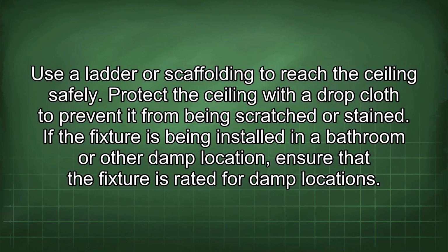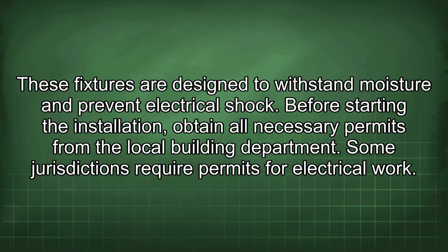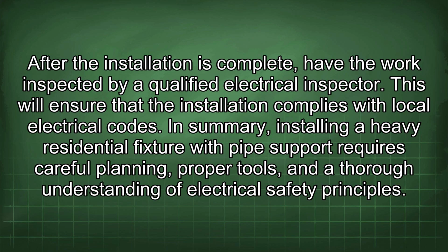If the fixture is being installed in a bathroom or other damp location, ensure that the fixture is rated for damp locations. These fixtures are designed to withstand moisture and prevent electrical shock. Before starting the installation, obtain all necessary permits from the local building department. Some jurisdictions require permits for electrical work. After the installation is complete, have the work inspected by a qualified electrical inspector. This will ensure that the installation complies with local electrical codes.